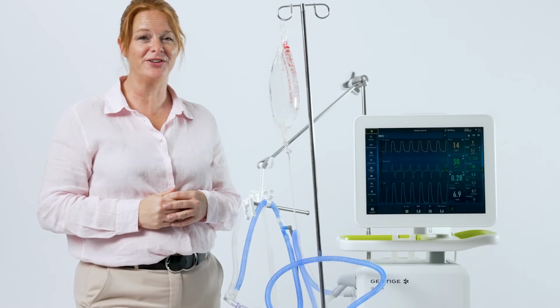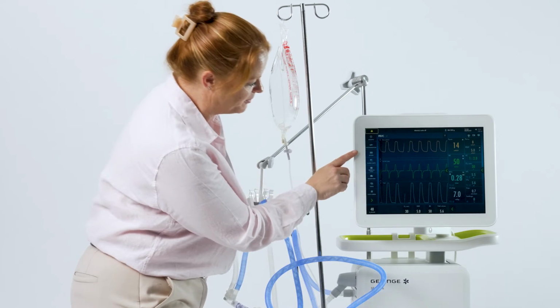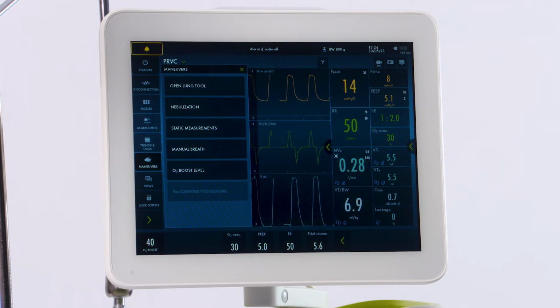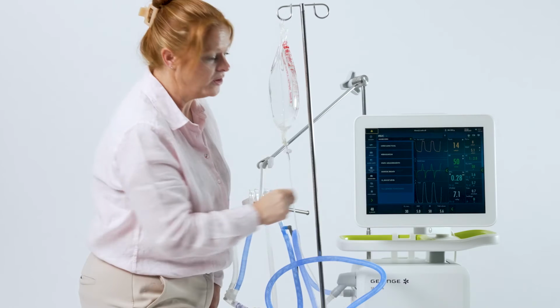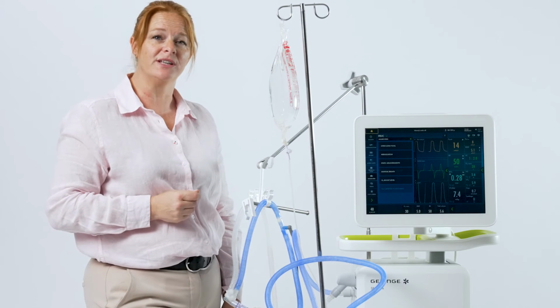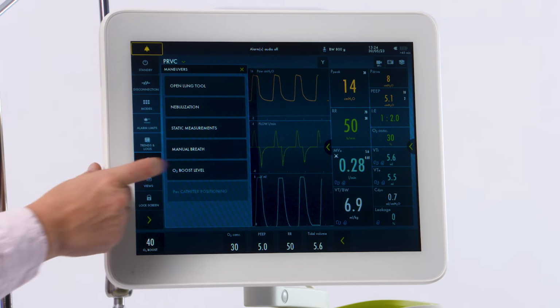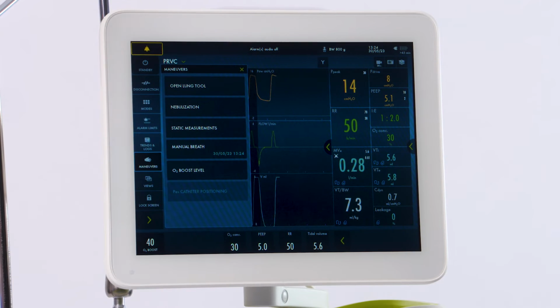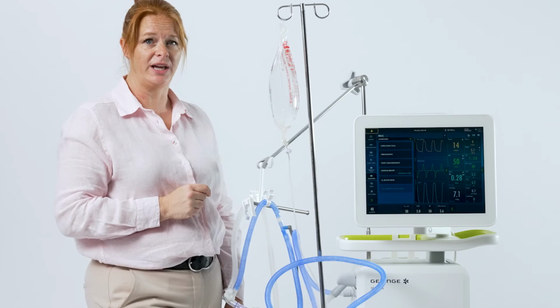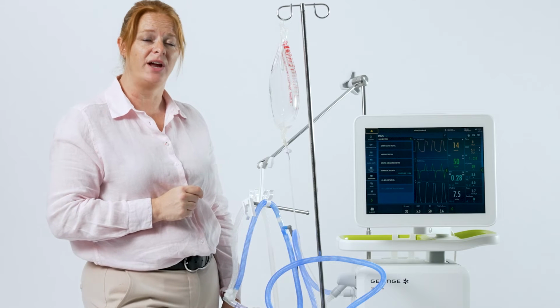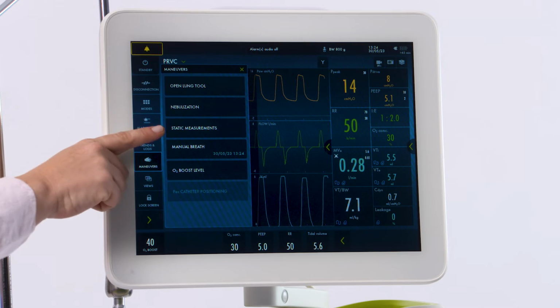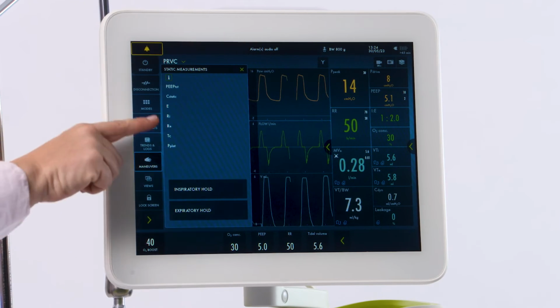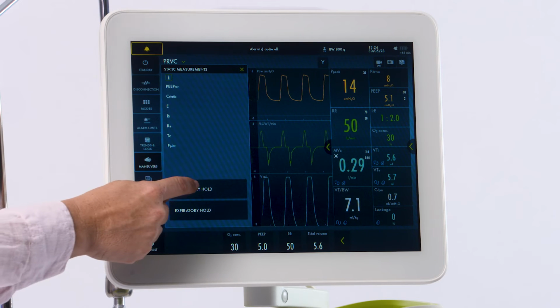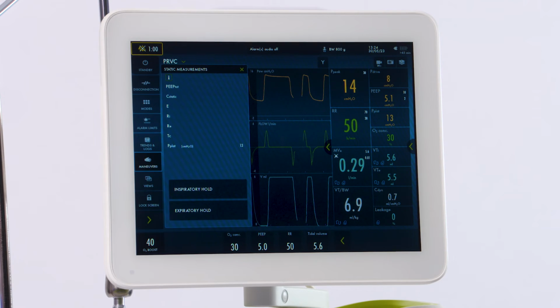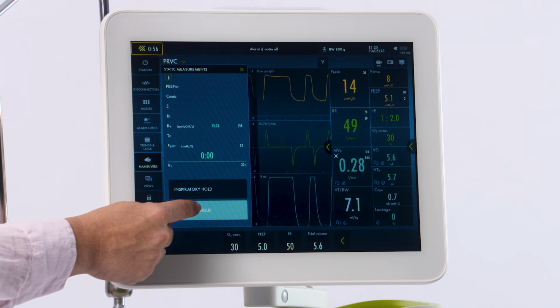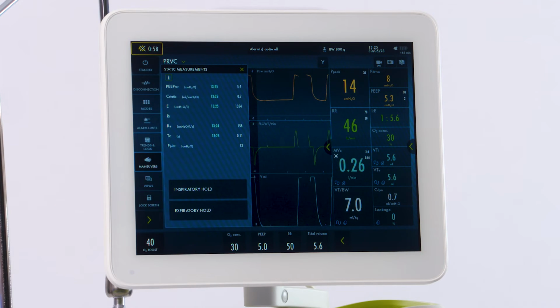Also located underneath your maneuvers tile is your manual breath. Select your maneuvers and manual breath. Every time you touch it, it will deliver your settings to the patient, touching and delivering a breath. Also located underneath this tile are your inspiratory and expiratory holds. Select static measurements and inspiratory hold. When you touch, it is active, and you can also do an expiratory hold. When it beeps, it is active.